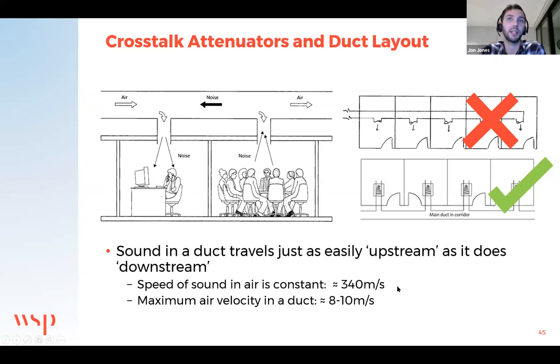Speed of sound is roughly 340 meters per second. Say the maximum velocity of air in a duct is 10 meters per second. This has very little effect on the overall or the net speed of sound, whether it's traveling up or down the stream in terms of the flow rate. So it should be considered that noise can travel, and does travel, both ways in a duct, not just in the direction of the airflow.